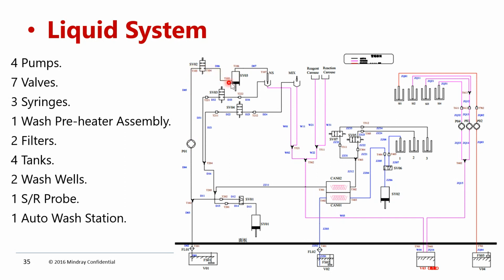Okay. So for cleaning the inner line with an effective wash, we need to use P01. You also have to verify this during priming. You can see the inner probe washing, whether it is coming with force or not. Okay. And other than this, these are the lines for low concentrated waste. Whatever water comes into the wash well goes to the external waste tank by gravity. There are no additional pumps used here.